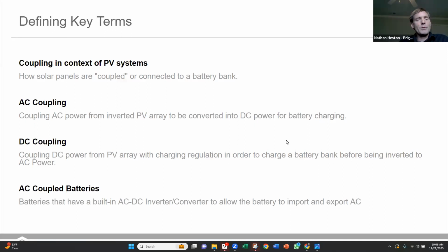You might have also heard of the term DC generators. There are generators coming to the market that produce DC power. And one of the reasons, as we'll get into, for wanting to feed DC straight to the batteries from different generating systems like solar or generators is to eliminate that extra inversion step, which can reduce efficiency. Typically, systems that are DC coupled can get higher overall efficiencies, around 92% or so round trip efficiency, versus AC coupled systems, which have lower round trip efficiencies, around 85%. However, there are other considerations to talk about, and we'll get into those.